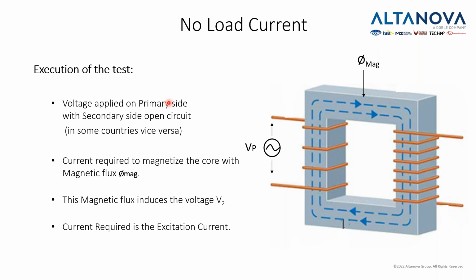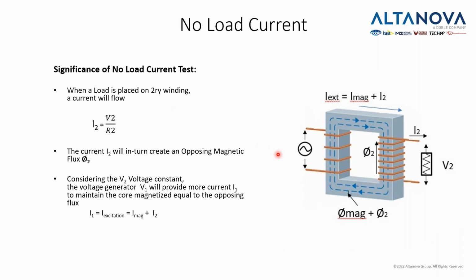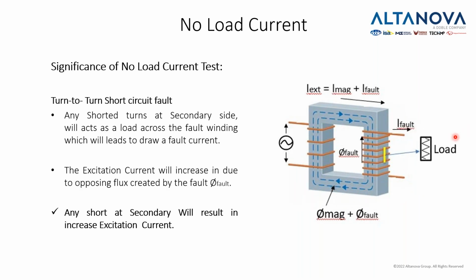So we have to generate on the primary side and basically measure the current which magnetizes the core. The transformer, if it wants to function, needs to magnetize the core. Having said that, I need to emphasize that in some countries it's done vice versa. So we are generating on the secondary side with the primary side open. Essentially, there is not much difference. It's just that we need to multiply that result with the TTR number, the transformer ratio of our transformer. In case we have some fault, let's say that these two windings are short-circuited, there will be a higher current getting into the transformer, and this will show that we have an issue with our transformer.